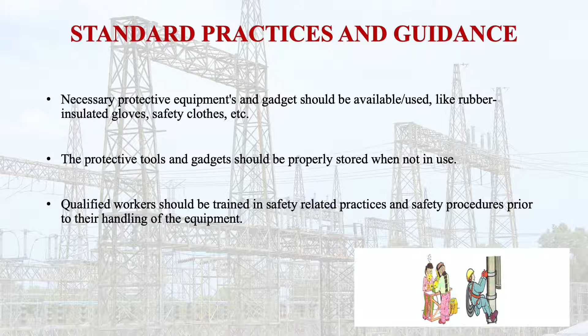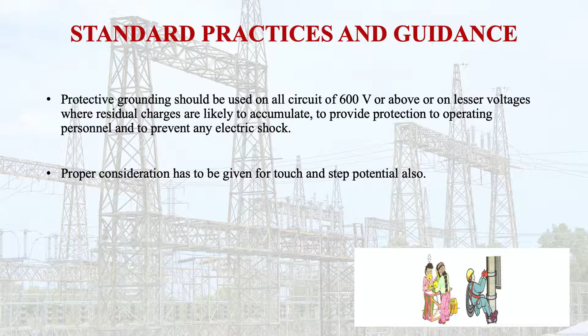The qualified workers should be trained in safety related practices and safety procedures prior to handling equipment. Protective grounding should be used on circuits of 600 volts or above, that means in the case of high voltage circuits, or even in the case of lesser voltage where residual charges are likely to accumulate, to provide protection to operating personnel and to prevent any electric shock. And proper consideration has to be given to touch and step potential also, which we have discussed in the case of earthing.